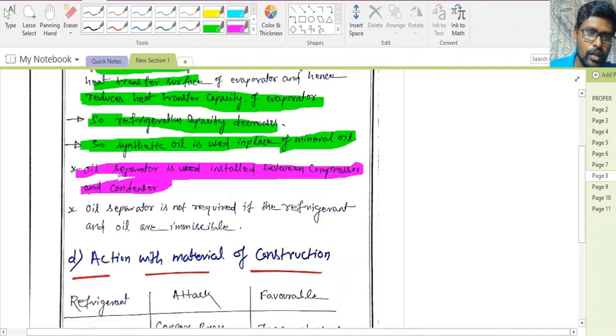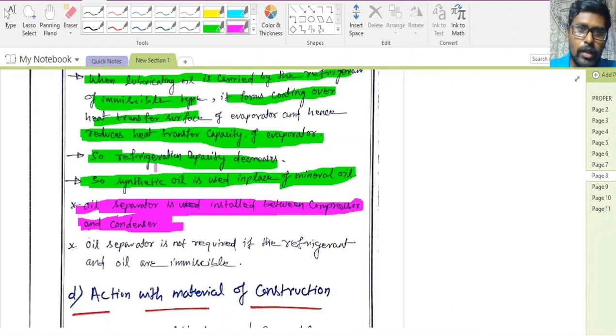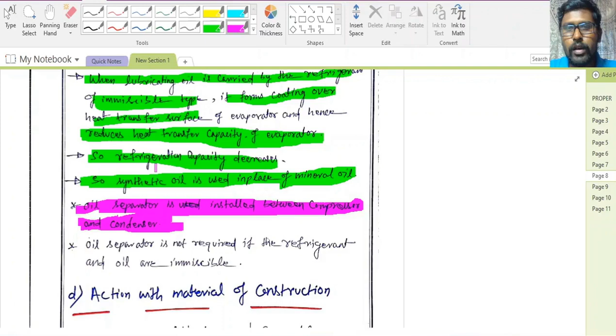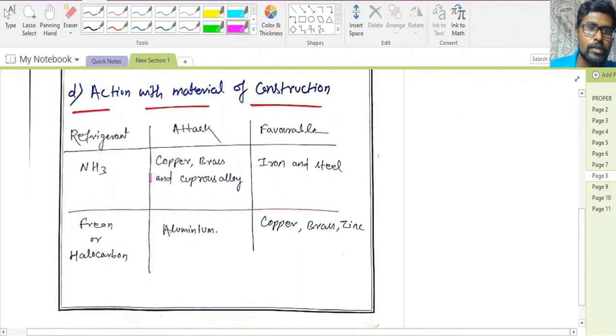Okay, next, if we use the oil separator, what will happen? When the refrigerant comes out from the compressor, the oil separator will separate the oil from the refrigerant and return it back to the compressor. This oil separator is used when the refrigerant is partially miscible with the oil. Okay, next is the action with the material of construction.